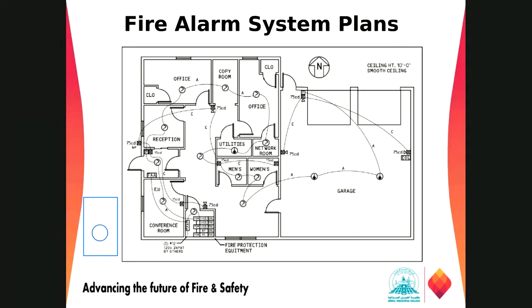If the area of the washroom is bigger, then we need a detector in those areas. Normally they install the heat detector, and this is an NFPA requirement, because we have to make sure that the steam and the vapors coming from the water do not affect the activation of those detectors. So normally the heat detector is required based on the area, but the contractor might have installed it mistakenly, or they did not follow the rule. That is another case.